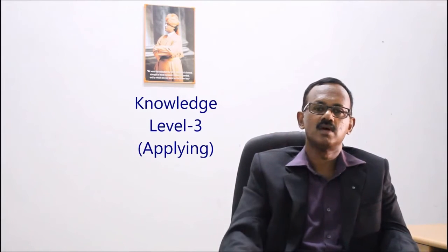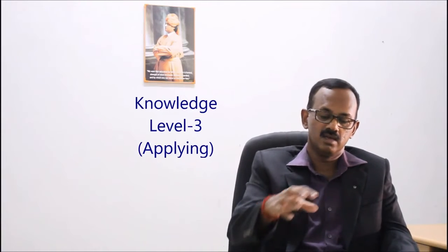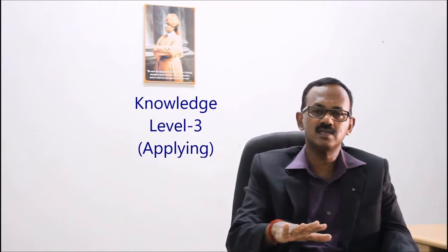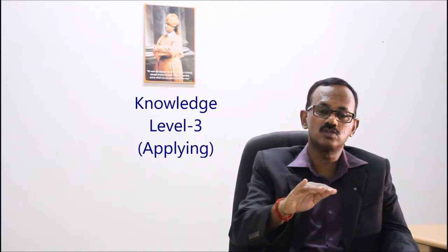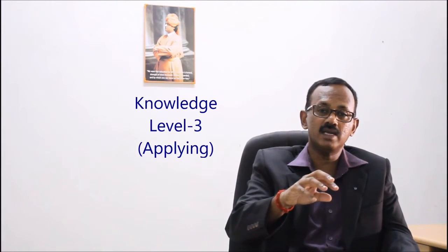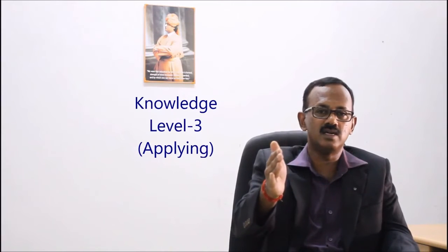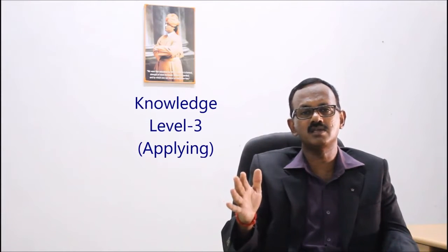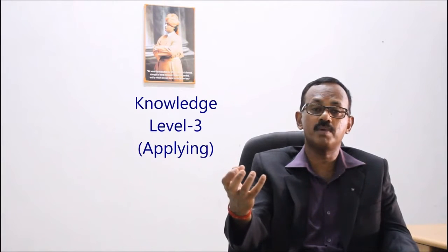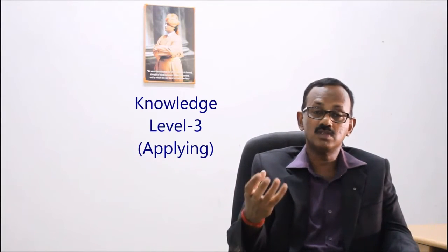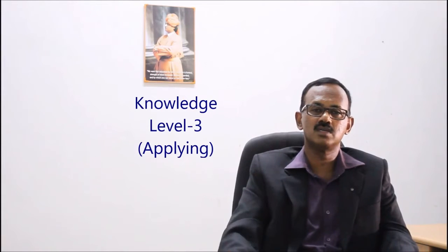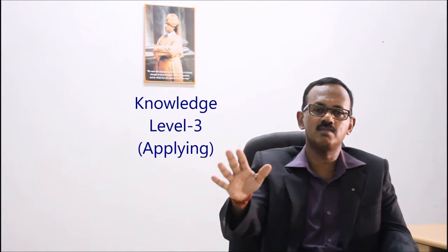Therefore, adjustments will be made in the system until, when a 1 kg weight is placed, the digital weighing scale will show 1 kg. This is the process of calibration, and when any instrument is being used on a continuous basis, it will automatically require calibration to be done at definite intervals of time, and there are agencies to calibrate and certify that it has been calibrated, because only then does it mean that the instrument has the capacity to show the correct reading. Therefore, this is a classical example of how an instrument has to be calibrated, and the example which was used was how to apply concepts of calibration on calibrating a digital weighing scale.